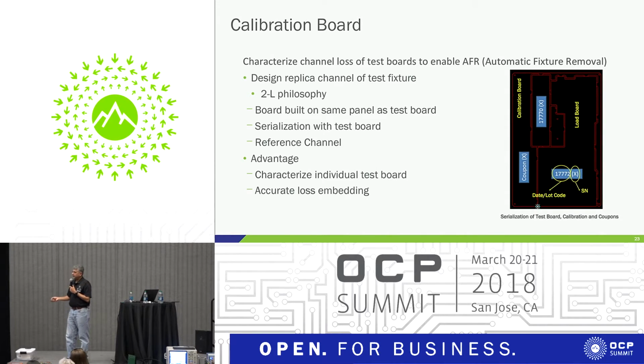So when you do any calibration using the calibration board, you have enough confidence that it is reflective of the actual test fixture. They are also serialized. Each of these fixtures is uniquely serialized, so you can identify which calibration board is used for each test fixture.